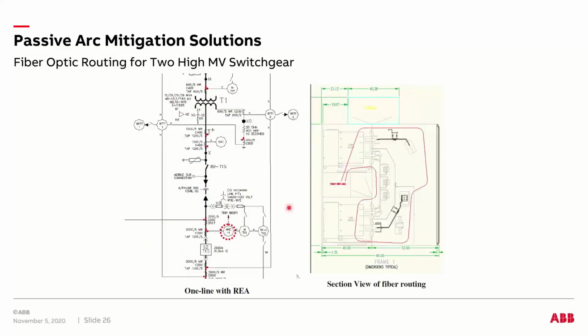So here is another depiction of you doing a fiber optic routing through the two high medium voltage switchgear when you have two breakers, right? So we can create a loop within each of that vertical section, where we can route the fiber optic cable through the breaker compartment all the way through covering the main bus compartment, the cable connection compartment, and then going back into the breaker compartment of the bottom breaker, right?